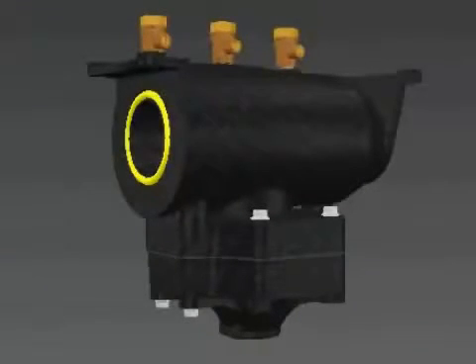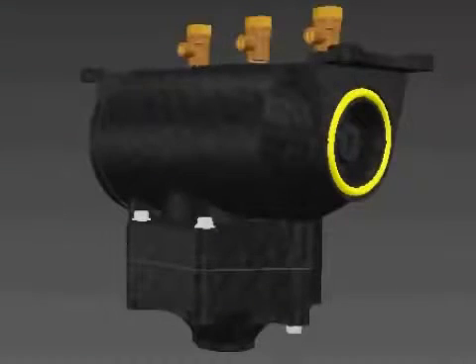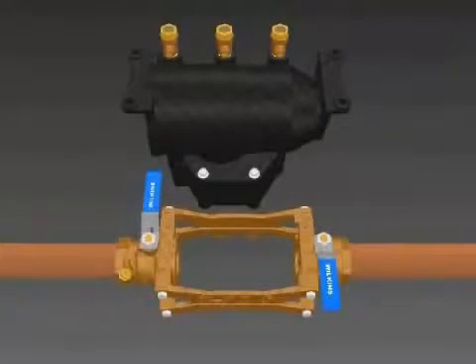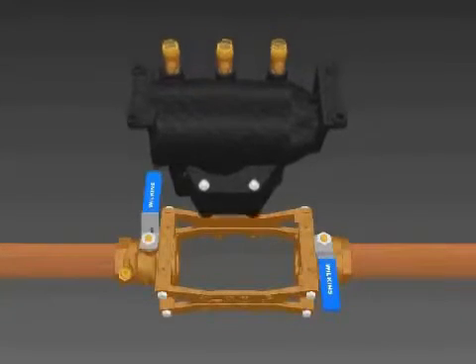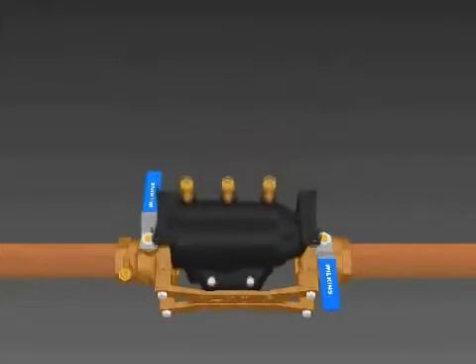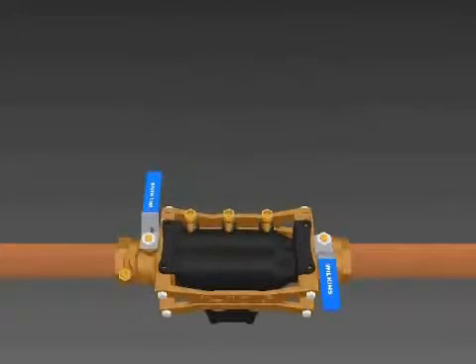Clean the O-rings at the ends of the housing and replace if necessary. Insert the two O-rings into the grooves in the housing. Lubricate the face of the housing O-rings. Make sure you have the housing facing the correct flow direction and place it down into the body. Push down with a rocking motion until the housing is down flush against the bronze body.